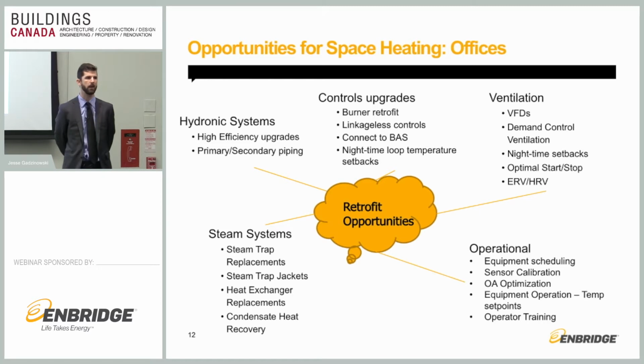Connecting any systems to the BAS, we find that a lot of older systems are still standalone and not really working with the building together. So connecting to the BAS is a good opportunity for upgrades. And then doing nighttime loop temperature setbacks, finding that in a lot of multi or mixed-use buildings, there are retail components of the building that have a 24/7 operation, say a Rexall or a Tim Hortons or something like that. So the building's supplying heat to the entire building and only to satisfy that one zone. So it's kind of rezoning, doing some night temperature setbacks and letting the building cool down a bit and only heating up those 24/7 zones. So it's a good opportunity there as well.